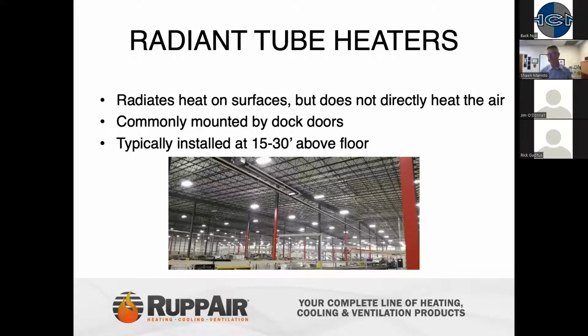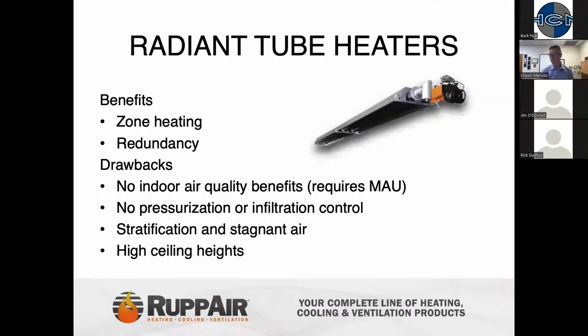Typically installed about 15 to 30 feet above floor level. The big benefits on radiant tube heat are having some of that zone heating capability, and they are good in redundancy because you're going to have several of them to cover a big type facility. Obviously, the drawbacks here are we're not bringing any air in, so there are no indoor air quality benefits from the standpoint of bringing in fresh air. Again, no pressurization control or infiltration control. And it's going to create, in some cases, stratification, also stagnant air. So if ventilation is not part of the equation, stagnant air can be a challenge here. And then higher ceilings sometimes make this product not available.